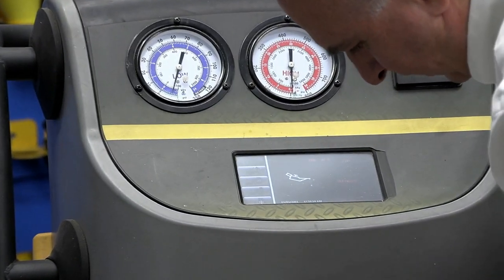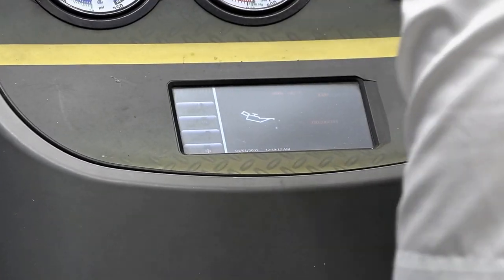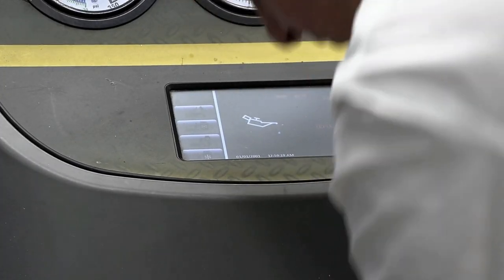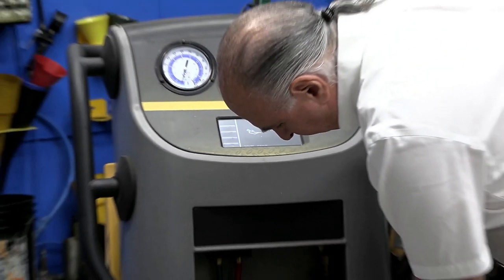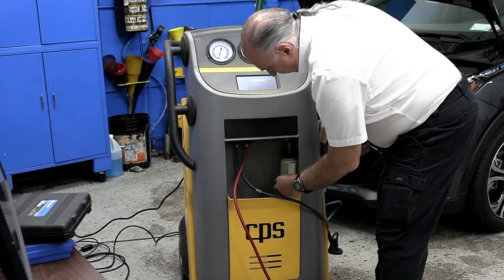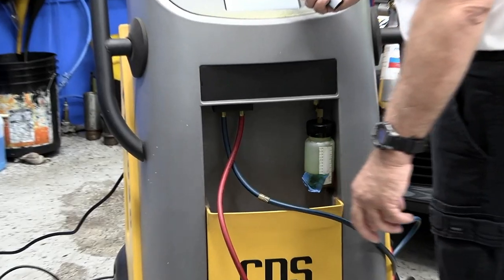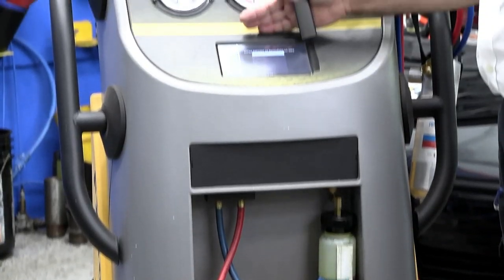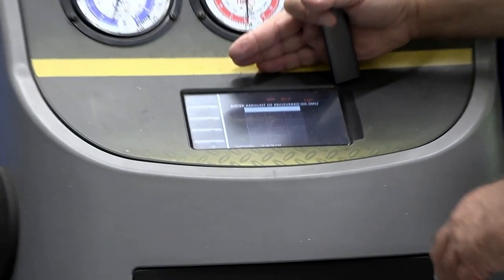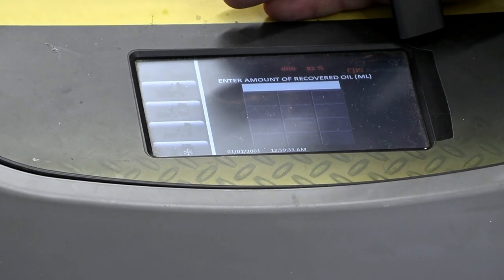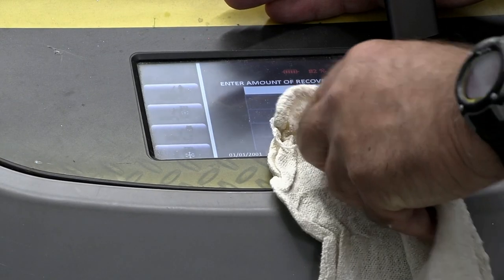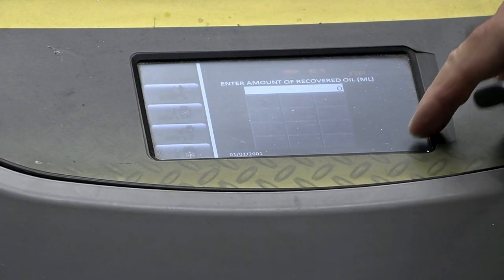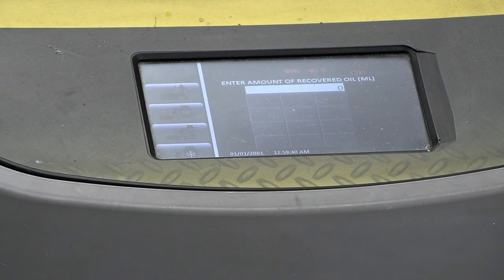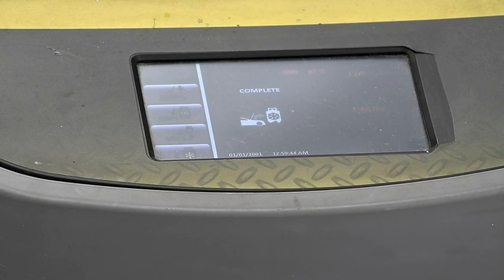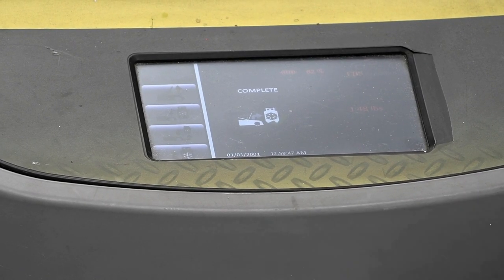Well, my tape fell, but basically right here, we don't have an issue with oil. How much oil came out? So we're going to put zero. Clean my hand here. And we're going to hit enter. So no oil came out, it keeps a record of that. That means it took the refrigerant out at a good pace.